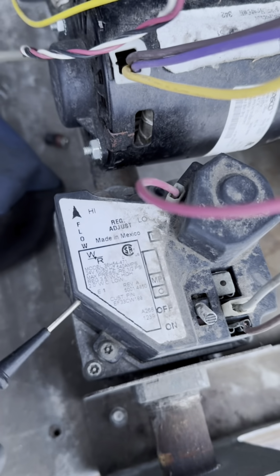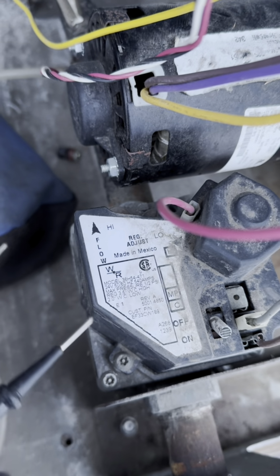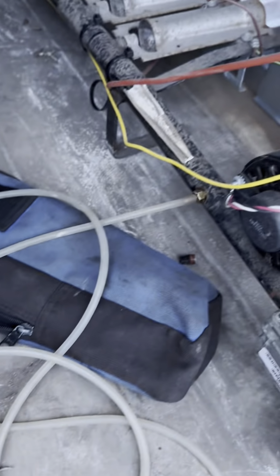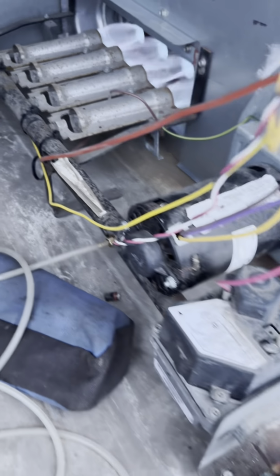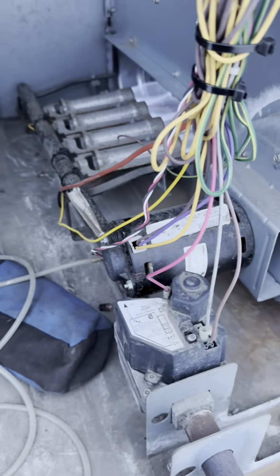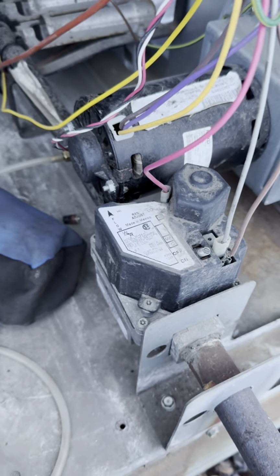This is a two-stage gas valve. The gas valve is saying high 3.5 inches and low 2 inches. Right now we're reading 2.1. It's a little bit on the high side. I'm going to go ahead and adjust that to 2. And I'm going to wait till second stage calls so we can see where we're at on our gas manifold.